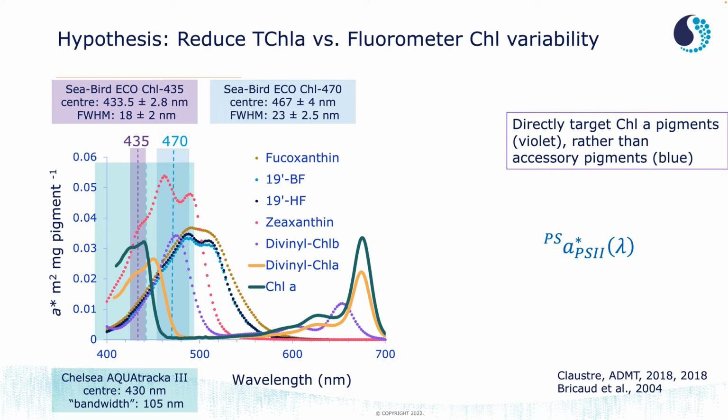Our current fluorometer uses the 470 nanometer blue LED. And you can see that it intersects a lot of those dotted lines, which are quite variable. Whereas when we use a violet LED, 435 nanometers, it intersects more directly the green and yellow photosynthetic pigments that we want, meaning chlorophyll A and divinyl chlorophyll A. So it's as simple as that. We're just going to change the color of the LED from blue to violet.